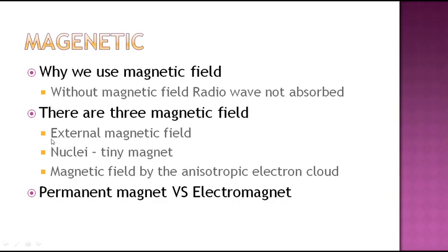And talking about the external magnet, there are 2 magnets possible. One is a permanent magnet, another one is an electromagnet. We can use a permanent magnet. That would be ideal, because every change in the magnetic field can affect the spectrum, and therefore using a permanent magnet is a good idea.